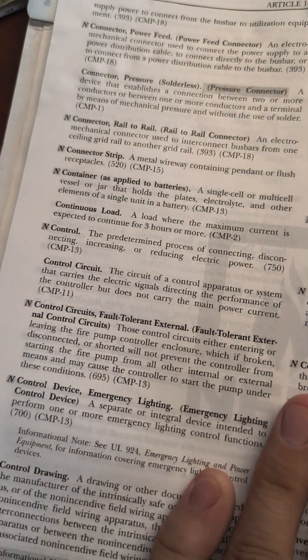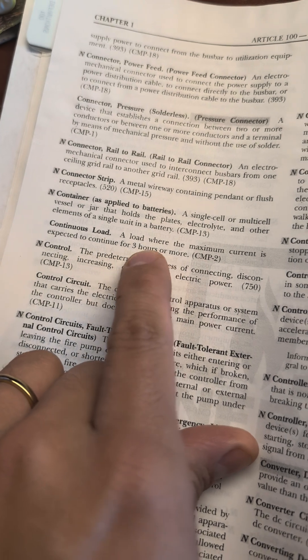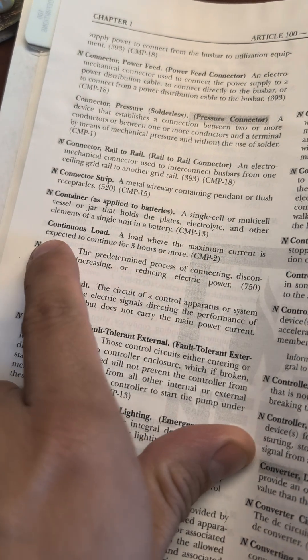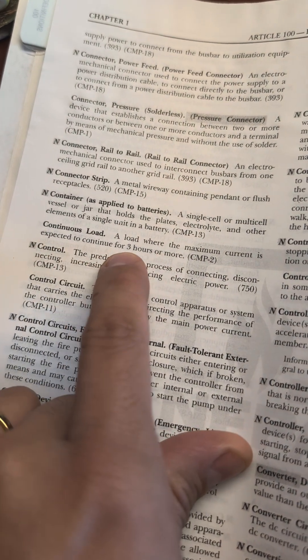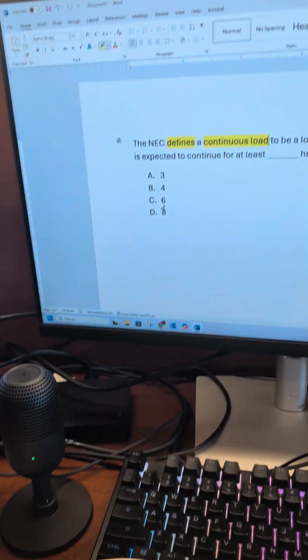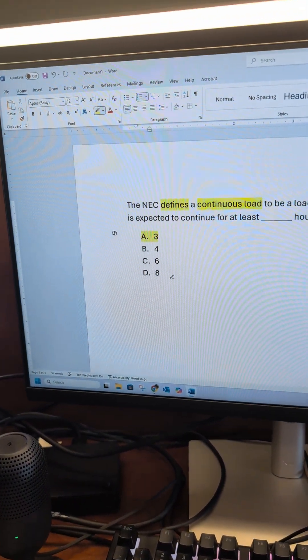Under C — continuous load: a load where the maximum current is expected to continue for three or more hours.